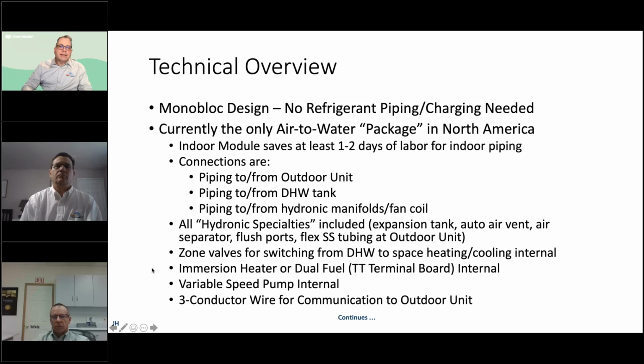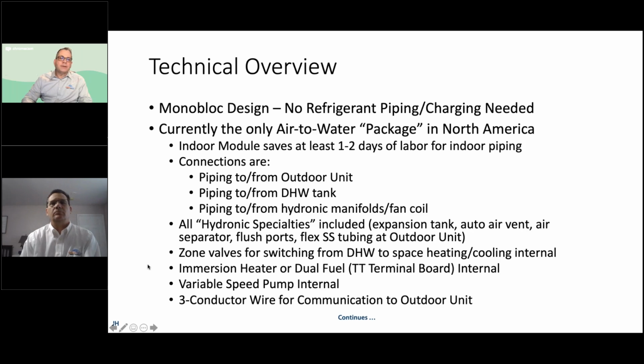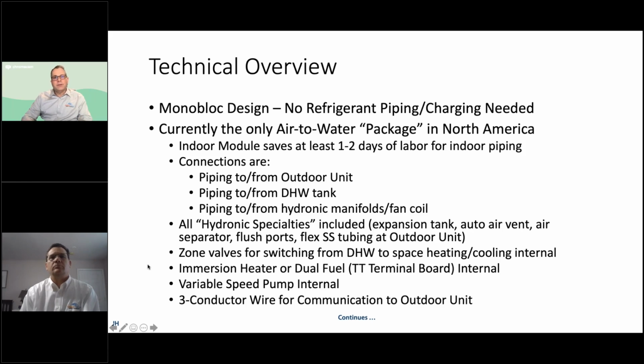The monoblock design, as I mentioned earlier, that's a European term, but essentially it means everything is inside a package unit. So we don't have to worry about refrigerant piping, charging, and we don't have any refrigerant inside the home. That becomes more and more important over time as the industry switches to different refrigerants. That'll be even more important. So this type of a design is much more installation friendly. It also allows us to check that unit at our factory in Mitchell, South Dakota. So it gets run tested, just like our geothermal heat pumps. That's a lot harder to do with a split system. Right now, at least, it's the only available package system in North America.